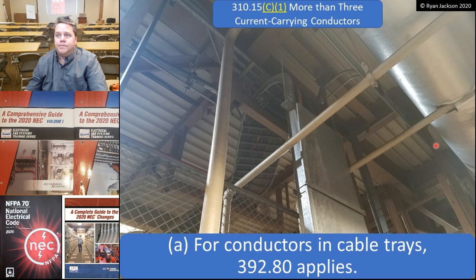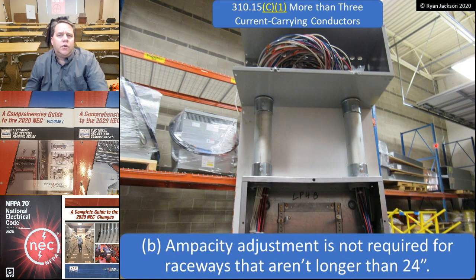The next thing that we read is subsection B, which says ampacity adjustment is not required for raceways that are not longer than 24 inches. Looking at these raceways here, it's quite obvious that we've got more than 3 current carrying conductors, but this raceway is less than 24 inches long.